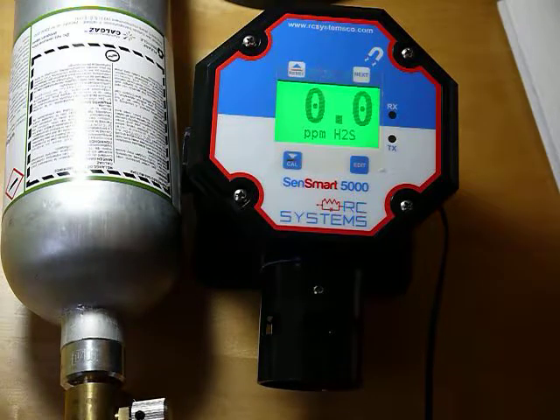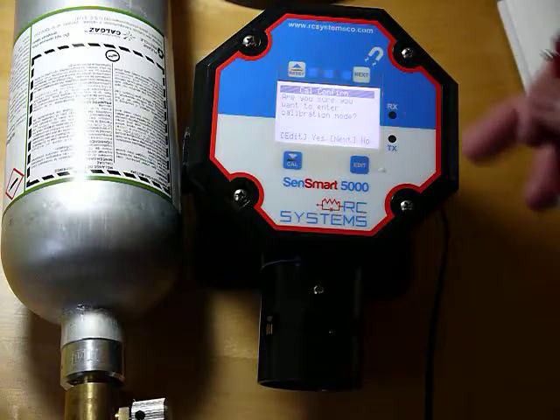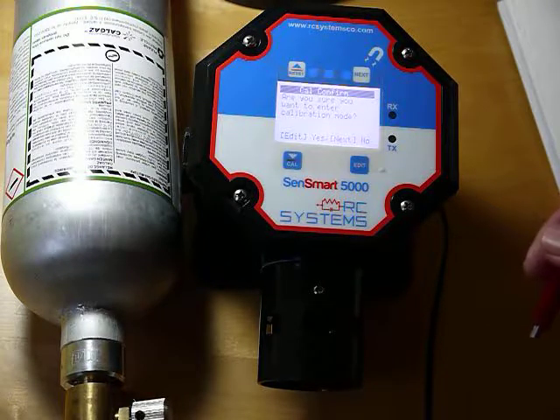Let's review the calibration of this transmitter. So it's an H2S transmitter, and I know it's been programmed to take 25 ppm H2S. I'm going to zero it first, so I hit cal. It asks me, do I want to go into calibration mode? To do that, I hit enter, or sorry, edit, and so it's saying apply 0 ppm.